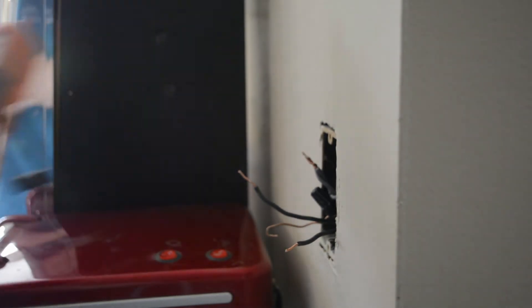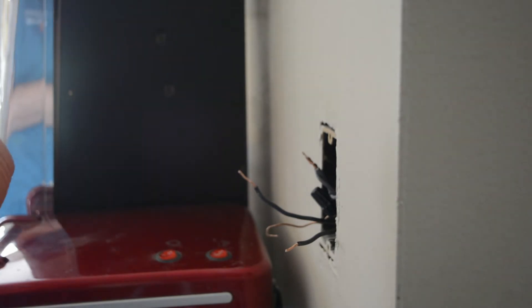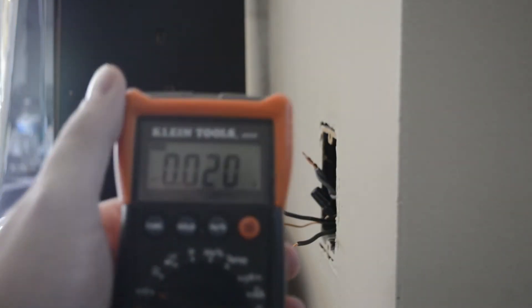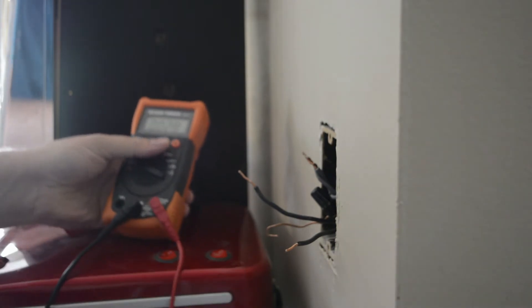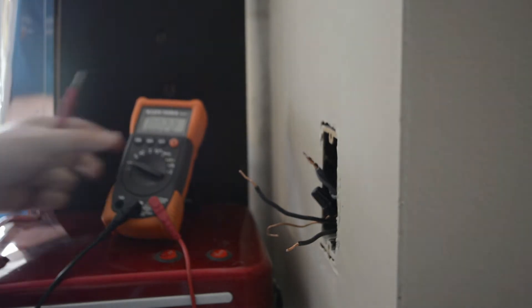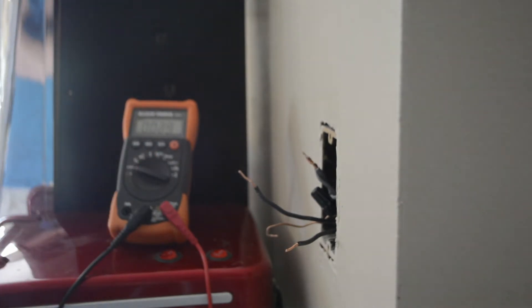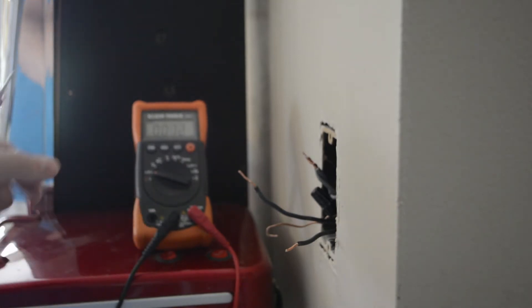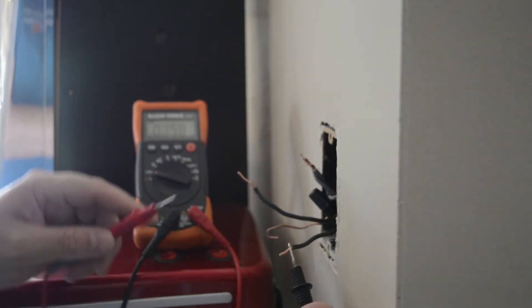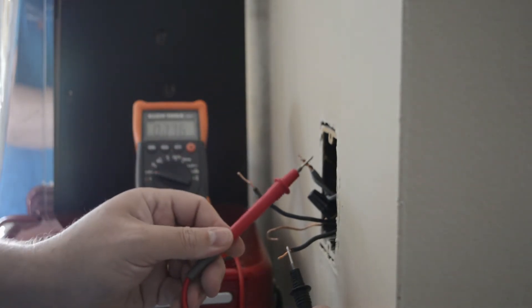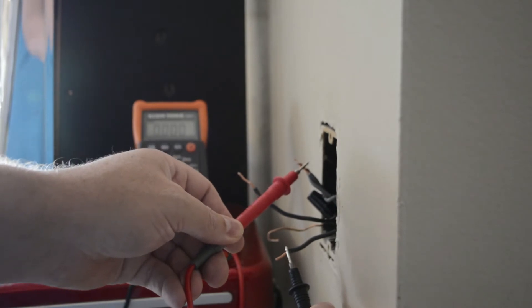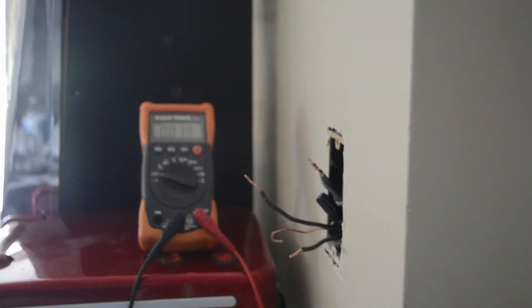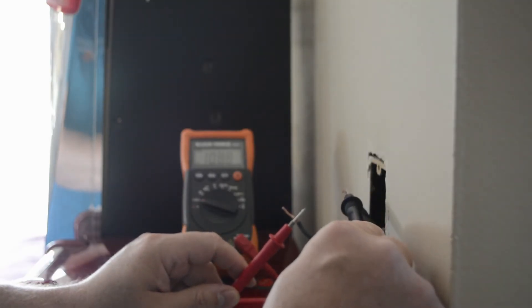So, power is turned back on to these switches. I'm going to use my multimeter which is set to AC. And I'm just going to test these leads so that I know which side is providing power. Make sure you can see that. So, if I touch here and to the neutral, I don't know if you can see that, there's no voltage on the multimeter. But if I touch this one and this one, I get 108 volts.